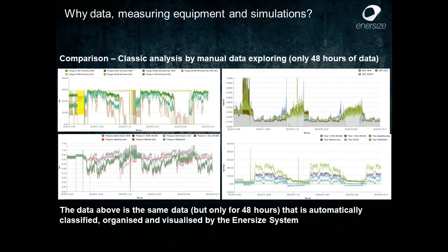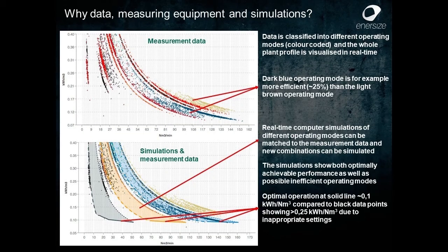That system I'm particularly proud to show you, where we organize cloud-based data, the big data, into different operation modes in colors, and the whole plant profile is visualized in real time, actually. And you can see here, if you need around 100 cubic meters per minute, you should operate in the dark blue mode rather than in the light brown mode. And the saving potential is obviously around 25% as you go from key performance indicator 0.12 up to, let's say, 0.16.